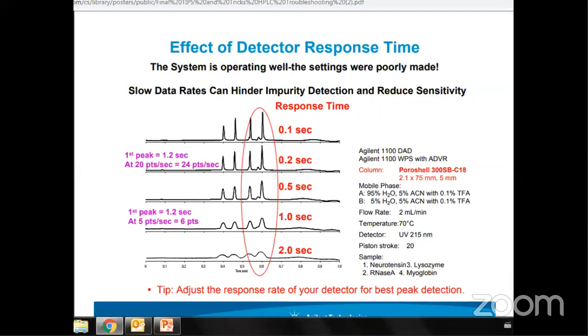So in this slide, I will again go to the same point and discuss it. Detector response time is also crucial for detection. If your detector setting varies during the operation, you'll find a lot of challenges. If the data acquisition time points in the detector are more, you will find good peak shapes and the sensitivity will be high. If the data point collection is low, it will reduce peak identification and the separation will also be less.